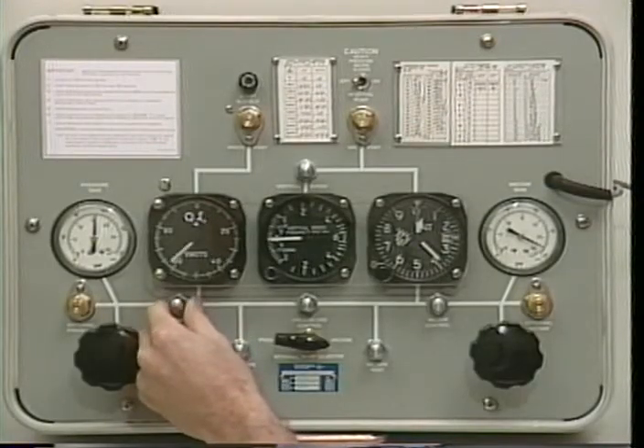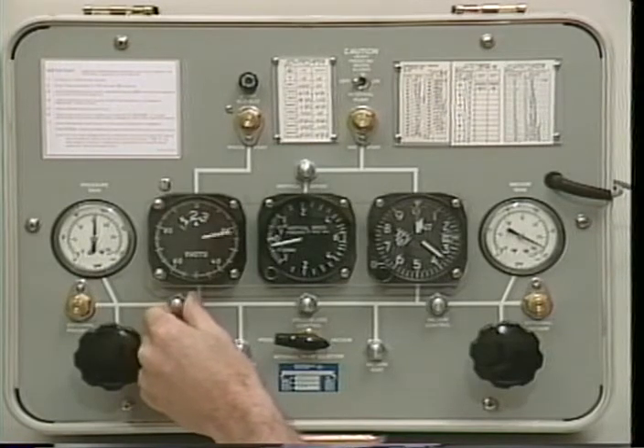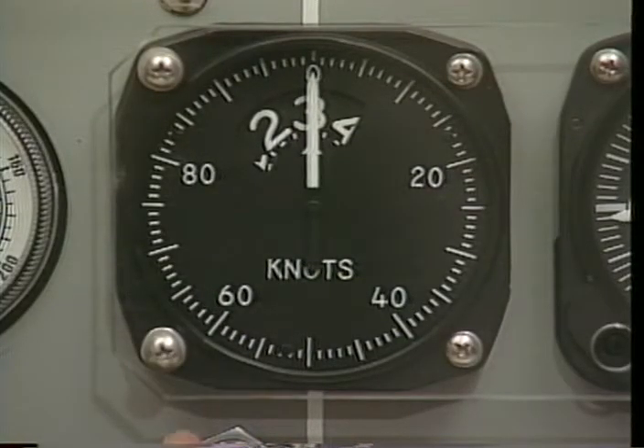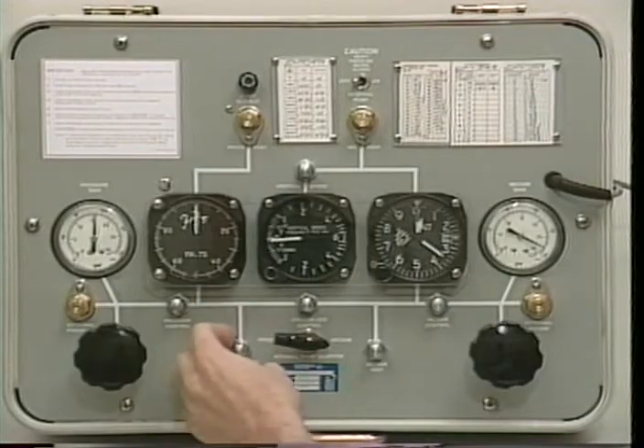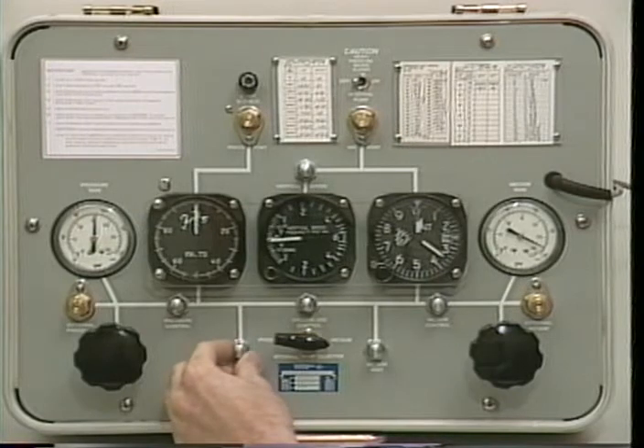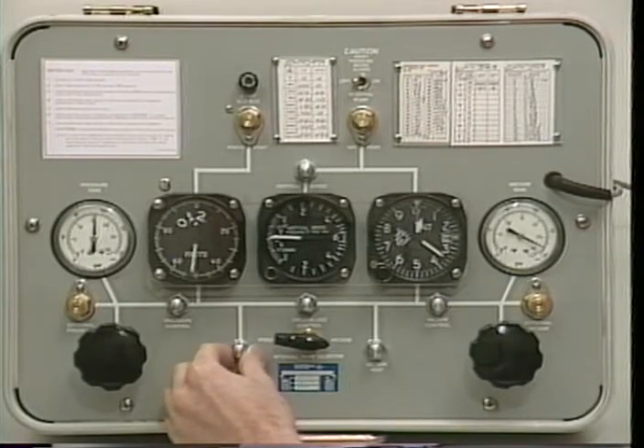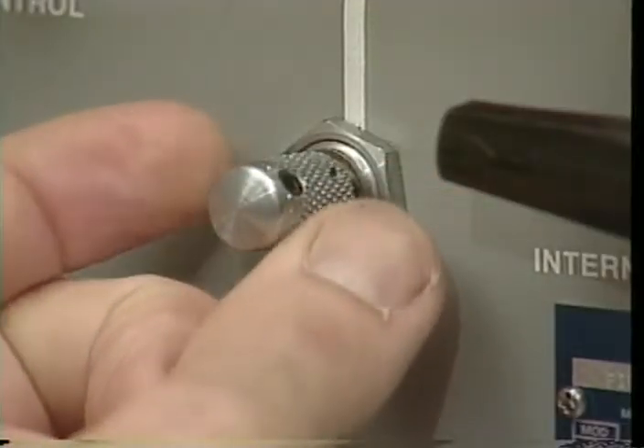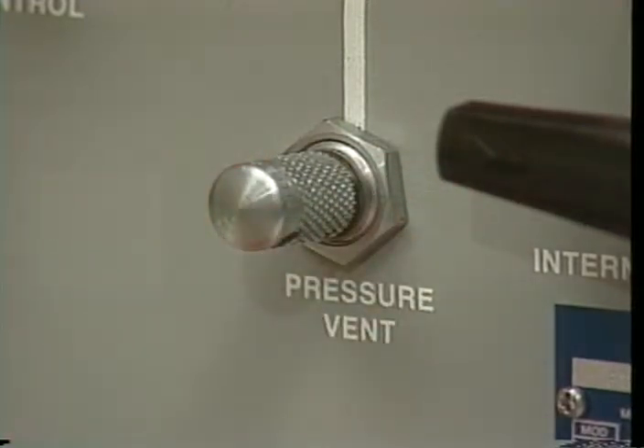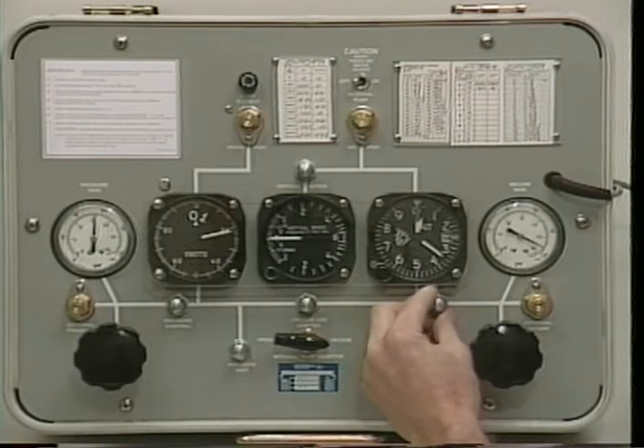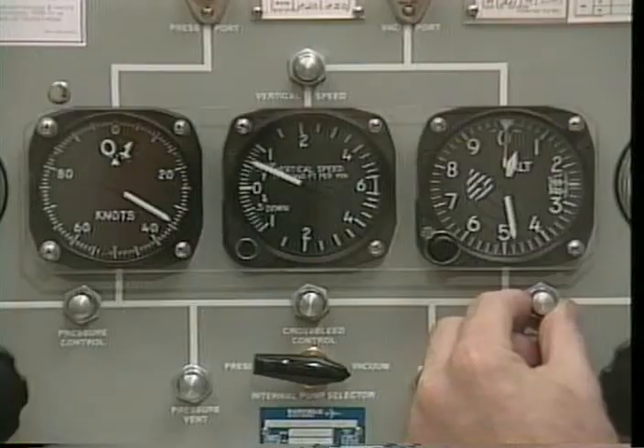Release pressure to the pitot system by opening the pressure control and observe that the indicated airspeed increases. Close the valve and observe for leaks. Now, open the pressure vent. As the pressure vent opens, the airspeed returns to rest. Then close the pressure vent. Next, open the vacuum control valve. As the vacuum control opens, the tester draws a vacuum on the static system.